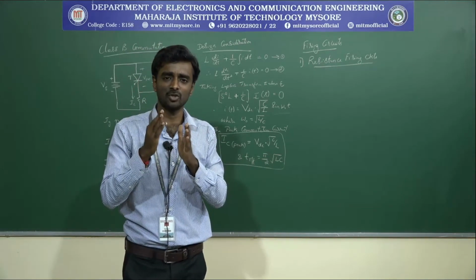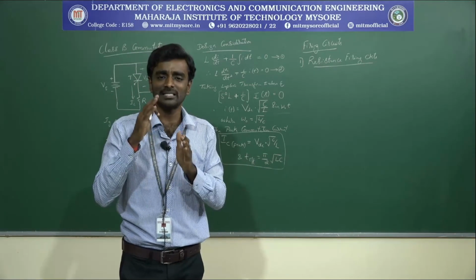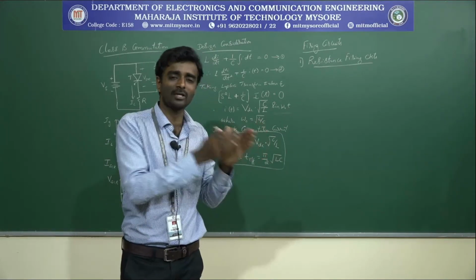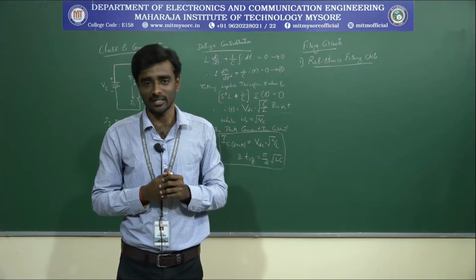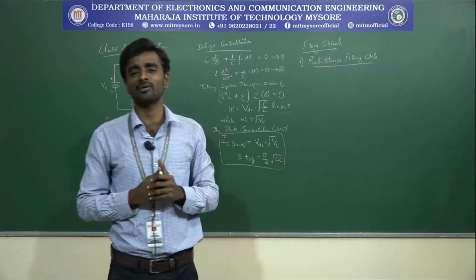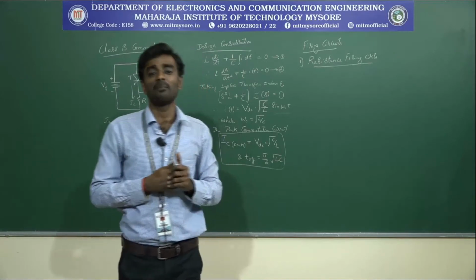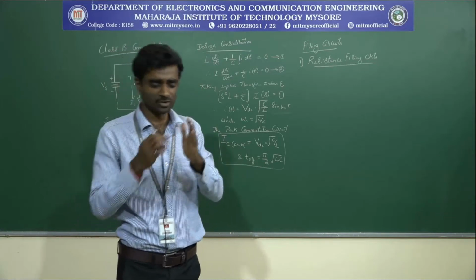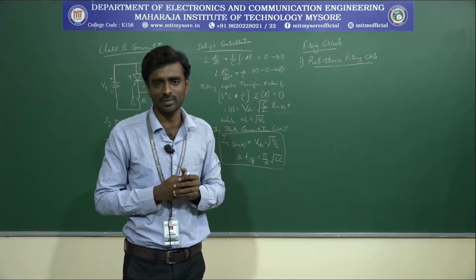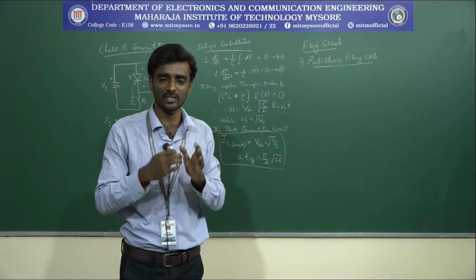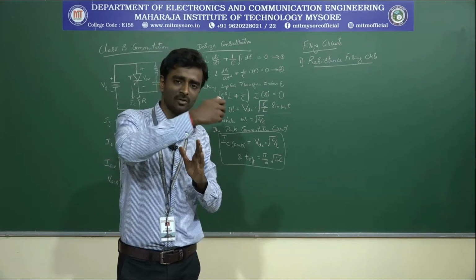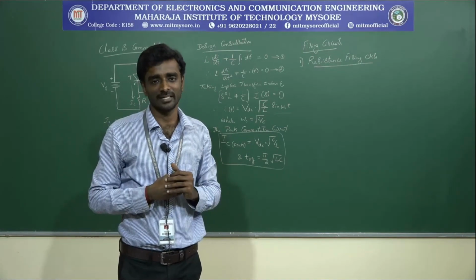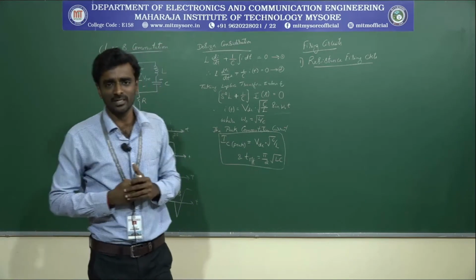You are making your thyristors to have an isolation, where this isolation will help your thyristor to operate at both low voltage and higher voltage. So how are you designing your isolation? By using a pulse transformer or an optocoupler. You can use optocouplers or a pulse transformer as isolation with respect to your thyristors, for working with low voltage as well as high voltage ratings. So that is with respect to their firing circuits.